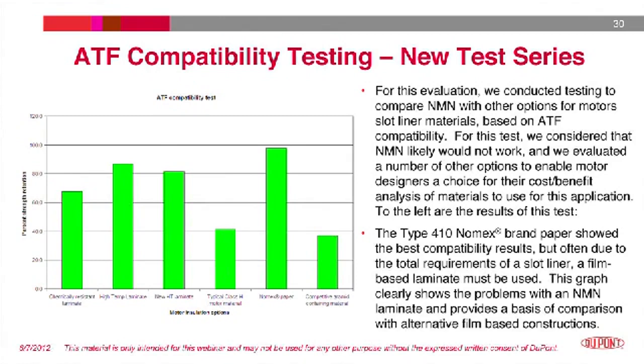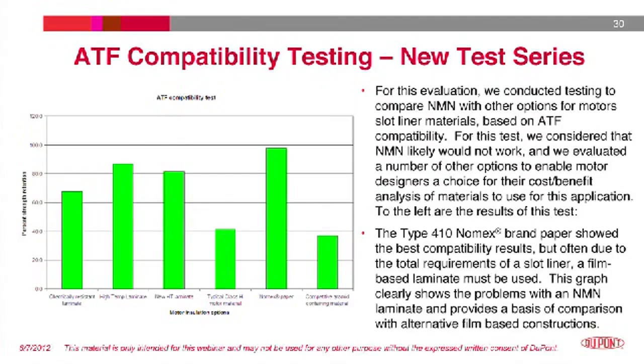Industry standard tests such as the motorette testing previously described in the prior example would have shown good thermal evaluations for the HEV motors, which typically operate at temperatures well below 180 C. However, it is this additional requirement of ATF compatibility that requires new materials and testing choices. DuPont has worked with several OEMs to help them understand other options to insulate their motors with the combination of thermal, stress, and chemical compatibility, as well as cost effectiveness in mind. Using a variety of laminated solutions from DuPont customers around the world, in this single test, we demonstrated a relative performance of these options.